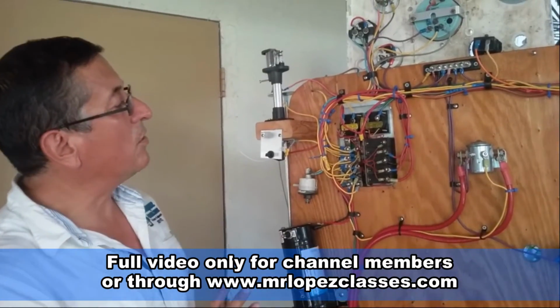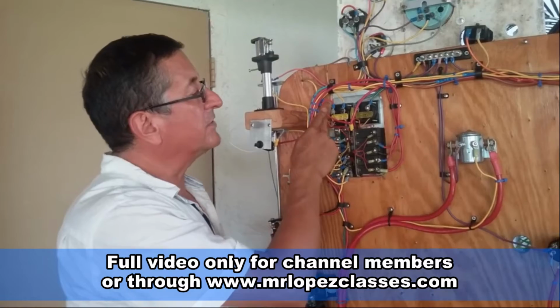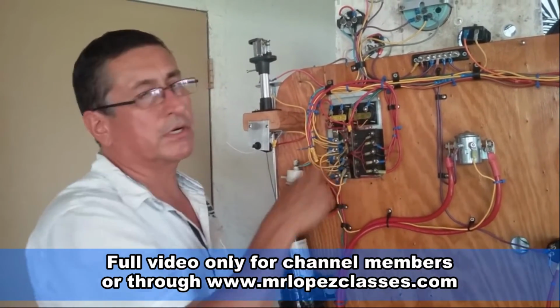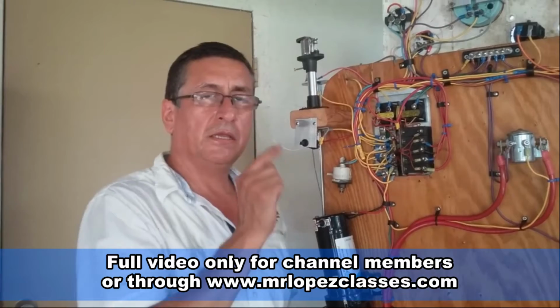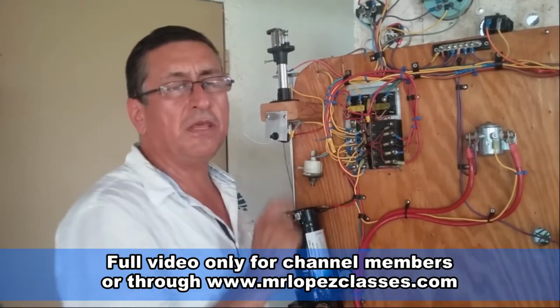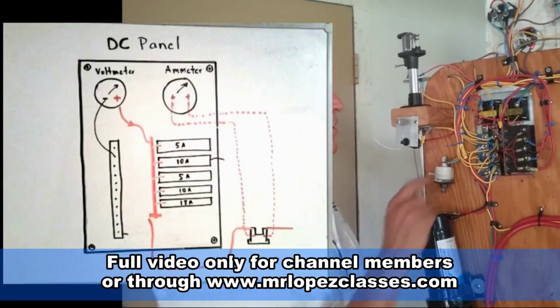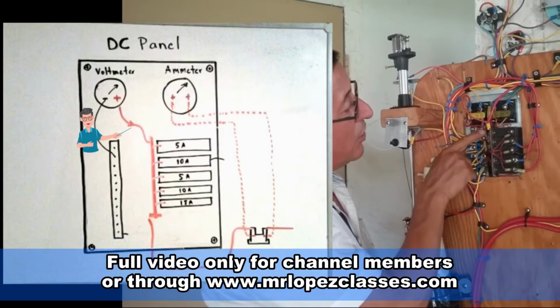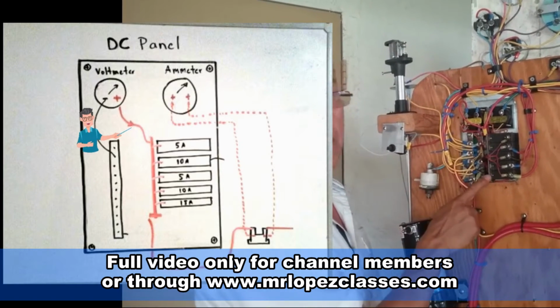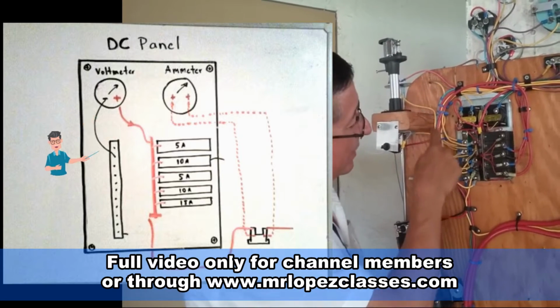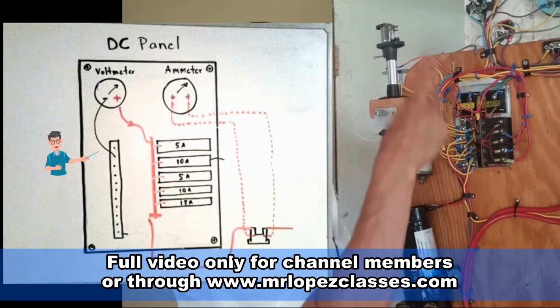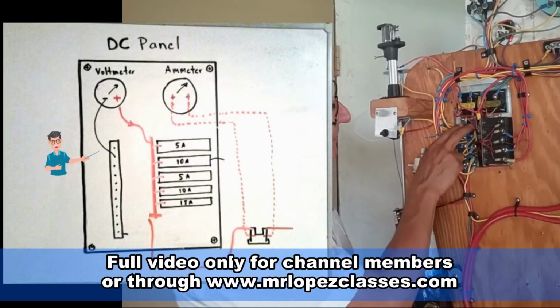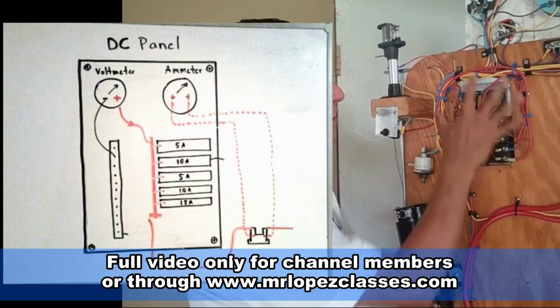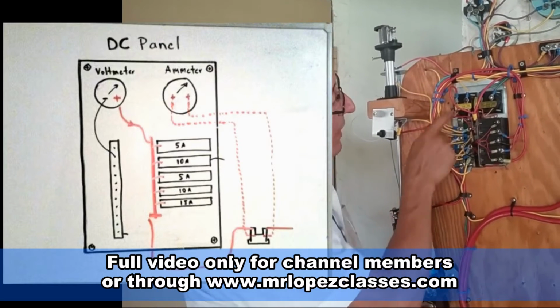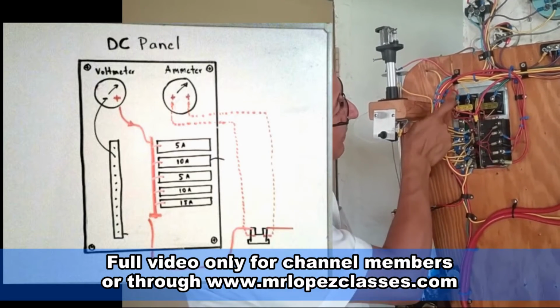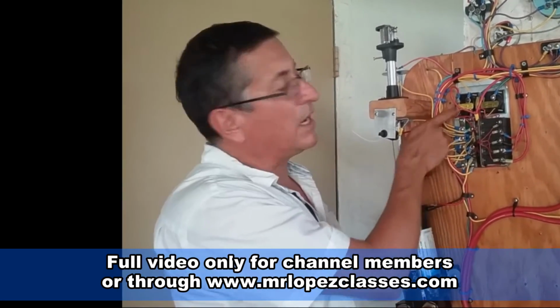Alright, right now I am going to explain the procedure to install the voltmeter and the ammeter. If you remember, in a previous episode, I explained how the voltmeter for a DC panel should be connected. The positive of the voltmeter is connected to any part of the positive bus bar, and the negative of the voltmeter to any part of any negative bus bar. In this particular case, this negative bus bar, because it's pretty close to the panel. Okay, the negative into the negative bus bar, and the positive here in the positive bus bar. And right now the voltmeter is working.